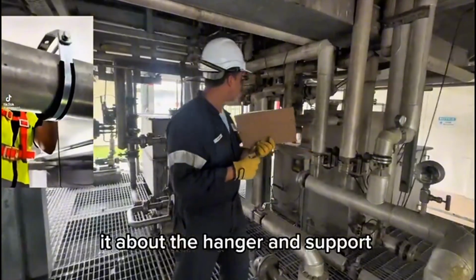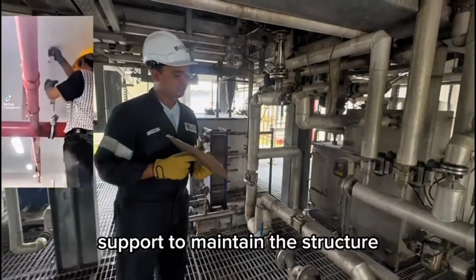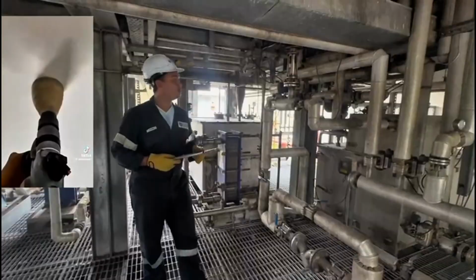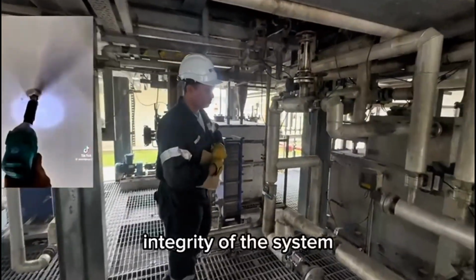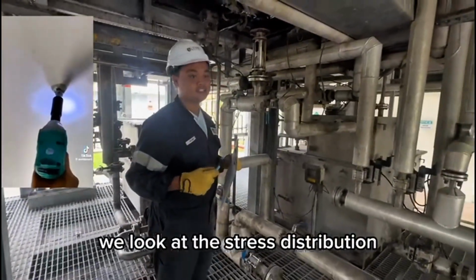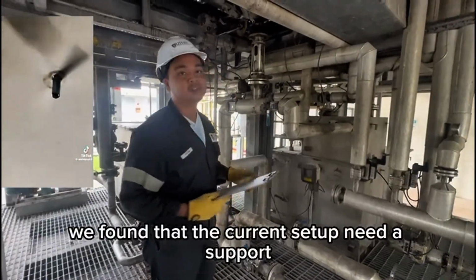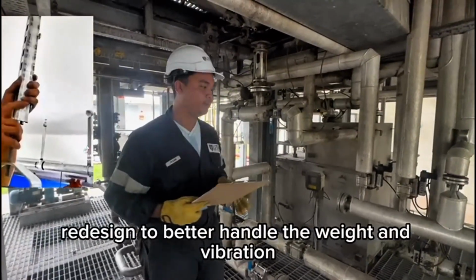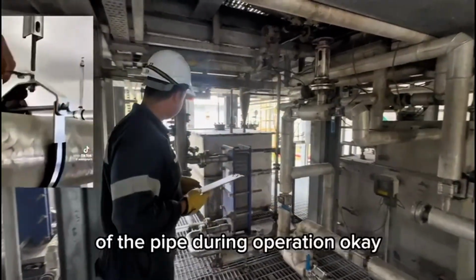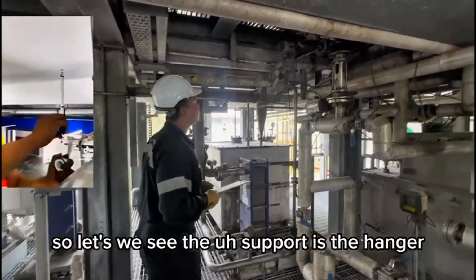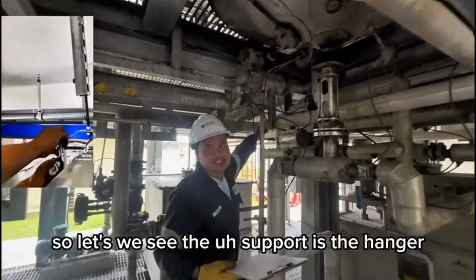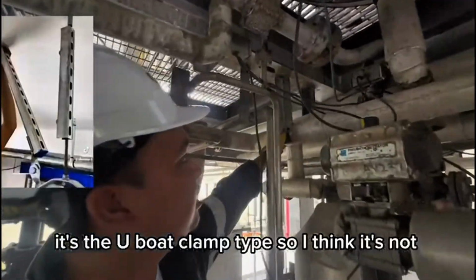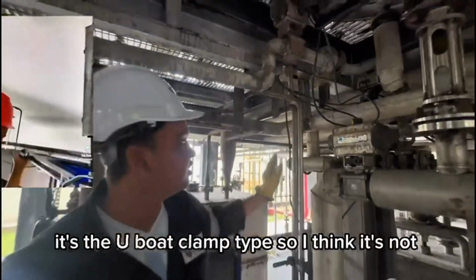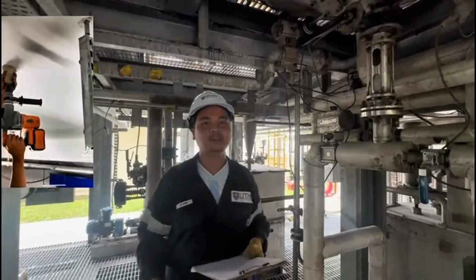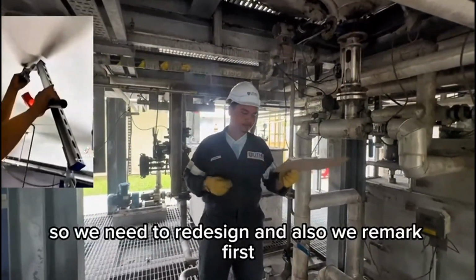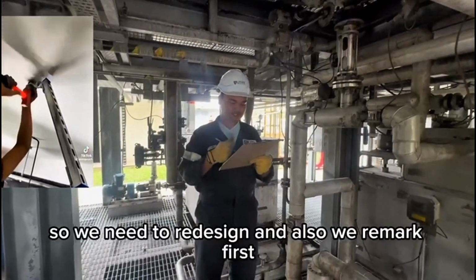About the hanger and support. To maintain the structural integrity of the system, we look at the stress distribution. We found that the current setup needs a support redesign to better handle the weight and vibration of the pipe during operation. Okay, so we see the support is a hanger of the U-bolt type. So I think it's not suitable for this setup, so we need to redesign.